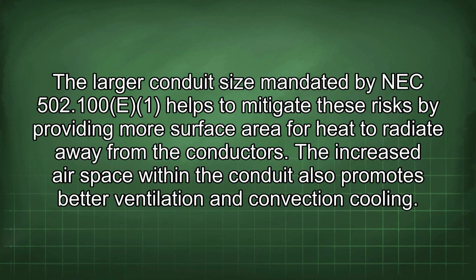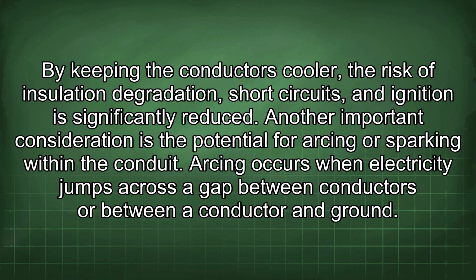The larger conduit size mandated by NEC 502.100 helps to mitigate these risks by providing more surface area for heat to radiate away from the conductors. The increased airspace within the conduit also promotes better ventilation and convection cooling. By keeping the conductors cooler, the risk of insulation degradation, short circuits, and ignition is significantly reduced.